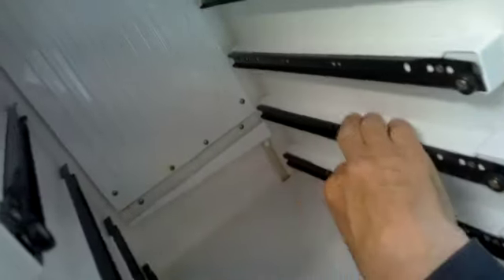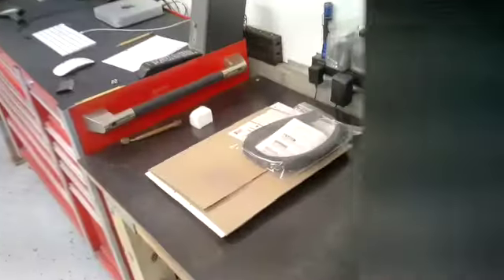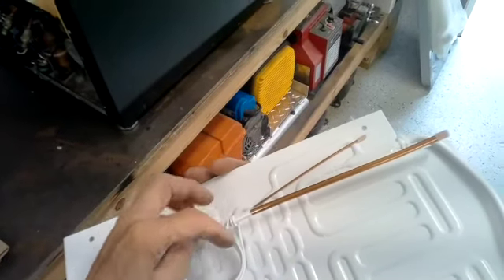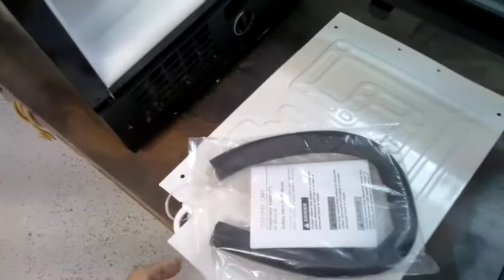Okay, so here we are. I got permission from the customer to go ahead and try to adapt the U-line evaporator plate and heat exchanger in here. So we're going to take out all these slides so we can get that evaporator coil out more easily. And then take the new evaporator coil and show you what we're going to do. As you can see, here's the heat exchanger. It goes through the suction line and comes out, wraps around it, that goes into the dryer. Okay, so it's going to fit in here, but I need to take those tracks out first to get it in there. And you can see it's a little bigger. I'll have to drill some holes. It's got the holes on the bottom. I might have to drill another hole in here, and maybe not. There's a hole over here, so we'll figure it out. But we're going to get started on this.